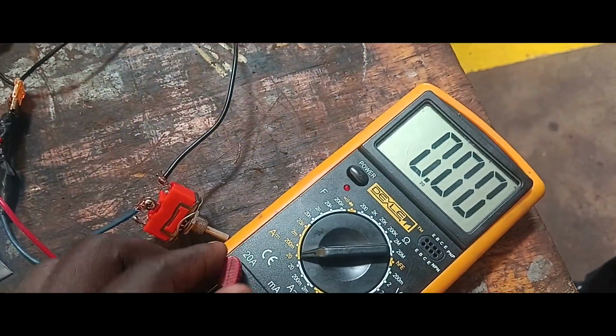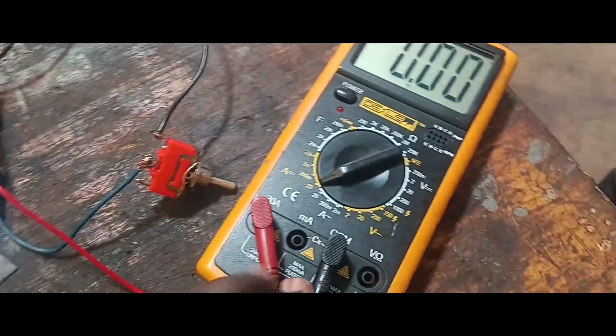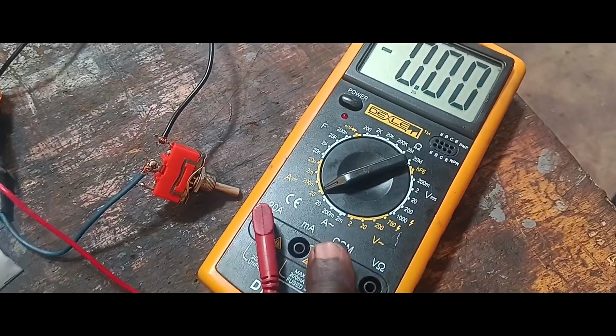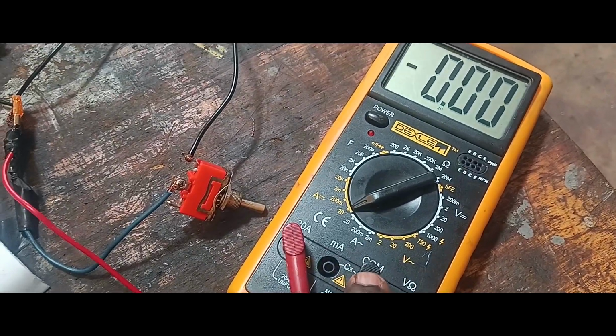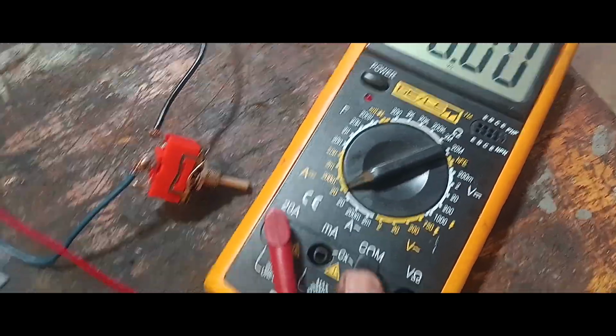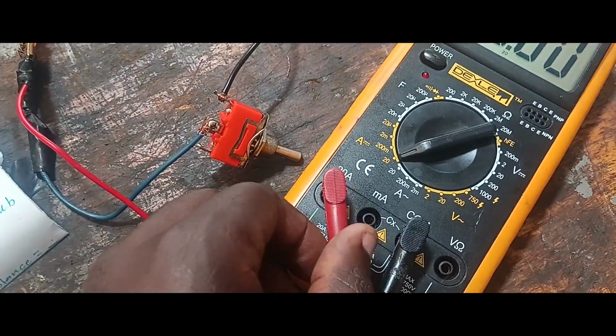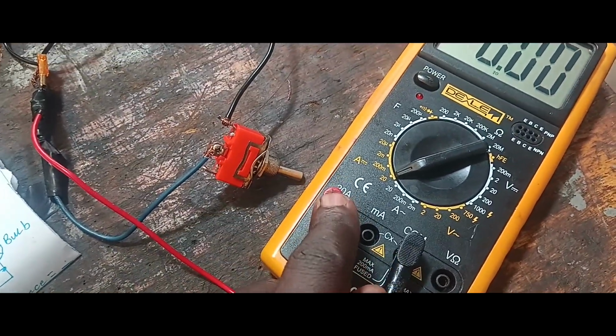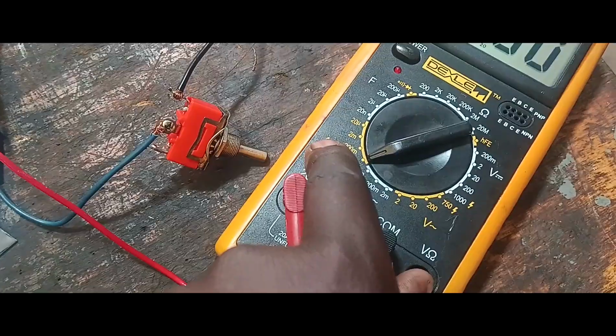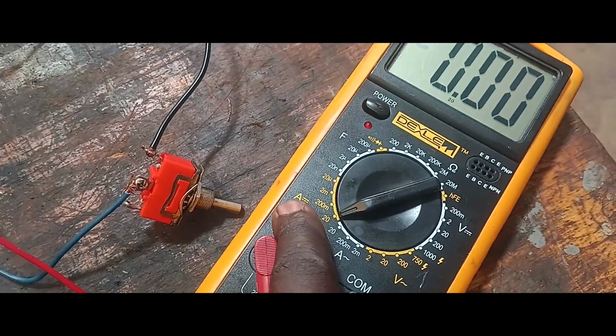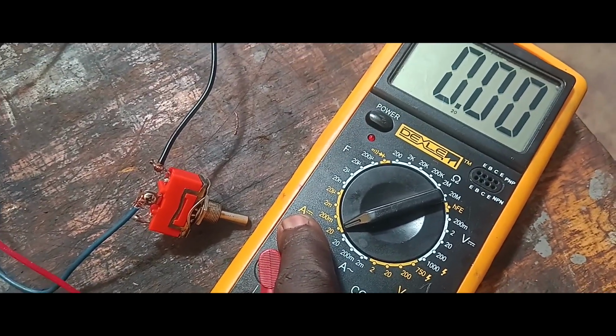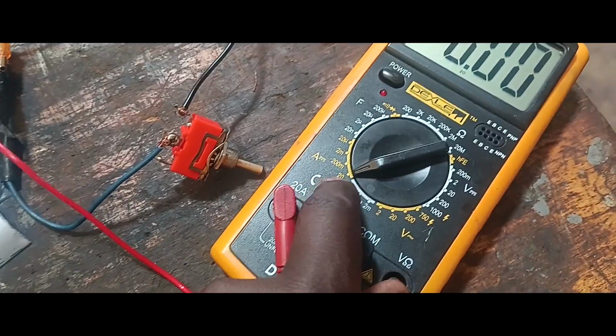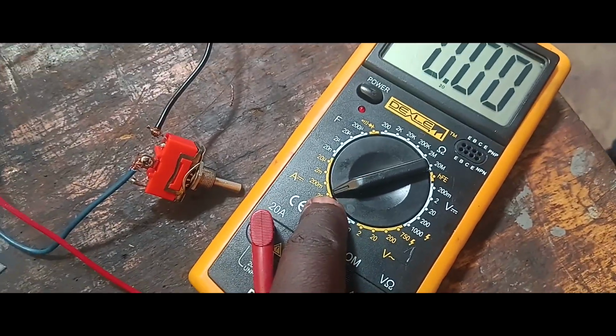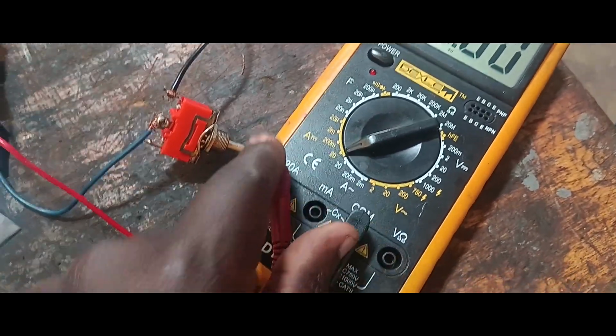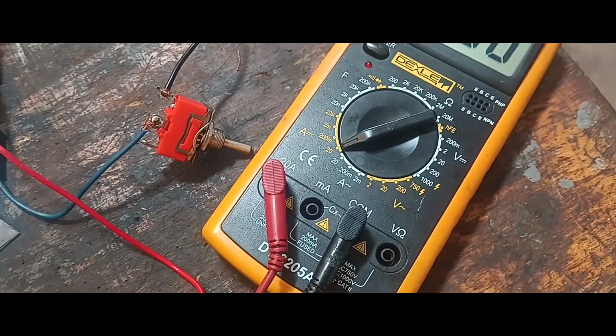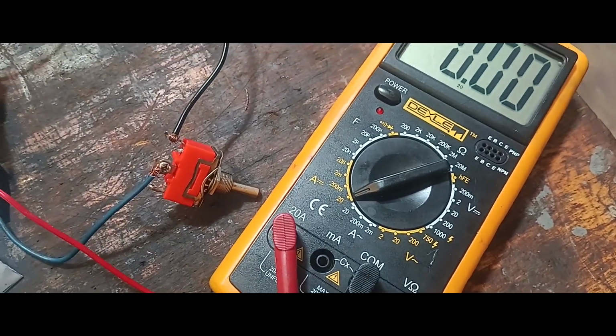Now we are measuring the current in the simple circuit. I want you to note this reading. We put the terminal of the voltmeter still at common, and the red probe goes to the 20 amperes port. Note that here now we have A, this is AC, this is DC current, and we want to deal up to a maximum of 20 amperes. That's how you set the multimeter in that setting to measure the current.